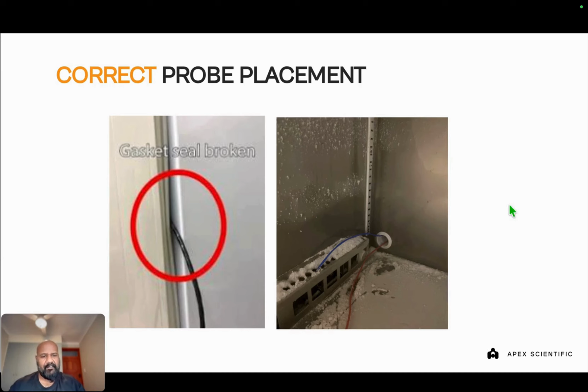BMS dry contacts - I don't ever see this these days, and I could barely find pictures for this, but all our freezers still come with this option. You can see that in the back of this freezer here, with some cables connected to this. All this is, is an open and close alarm, so this gives you access to the freezer alarm. Usually customers have BMS systems or building management systems, and you can connect with a cable directly to the building management system, so if the freezer alarms, they'll get an alarm in the building management system.